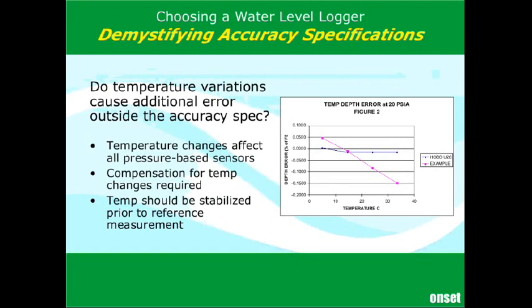There are temperature effects caused by the diaphragm connection to its own sensor housing, and there's an interaction as the temperature coefficients vary. There's also the interaction between the sensor housing and the logger housing — it needs to be a resilient mount, but it does have an effect on output. We also have the bridge circuit measurement response varying over temperature. All of these add up to a significant amount of error.